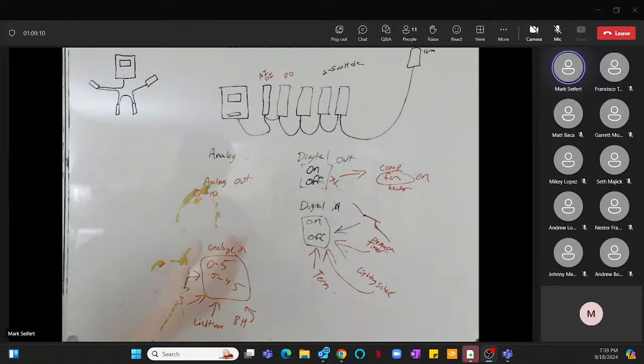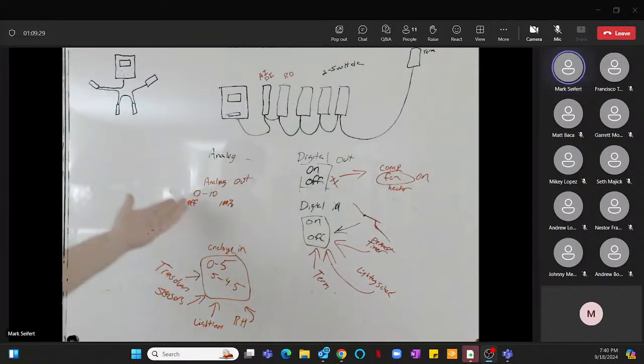Analog out, let's take for instance a condenser drive. We program it 0 to 10 volts for the most part, 0 being off, no speed, 10 being 100%. So if you want to test your analog outputs, the best way I've found is to set it to 100% and make sure you've got 10 volts coming out, then set it to 50% and see if you've got 5 volts coming out. If you've got that, you're pretty well assured it's calibrated.